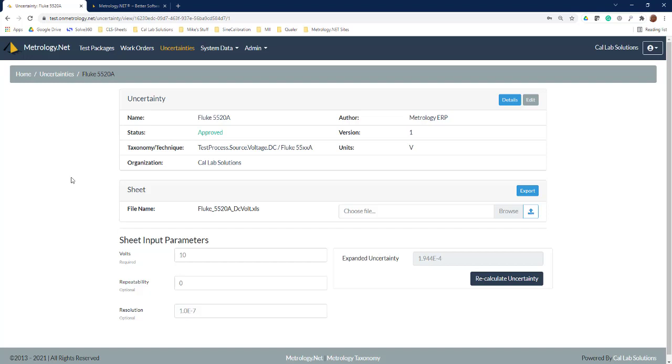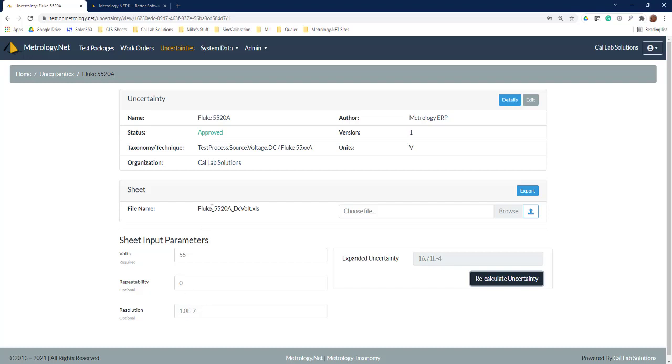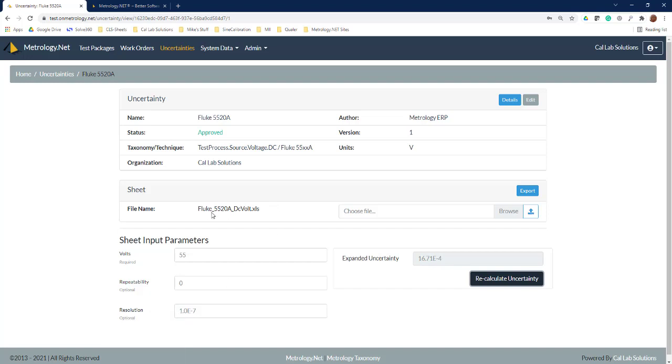This is going to pull up a measurement uncertainty calculator that's built into metrology.net. What you can see here is as I type in a value, say 55 volts, and I hit recalculate, it's going to calculate out my measurement uncertainty for 55 volts. You see I can put in a repeatability and I've got a default resolution of 1e-7, so all that data in there came out of a spreadsheet.